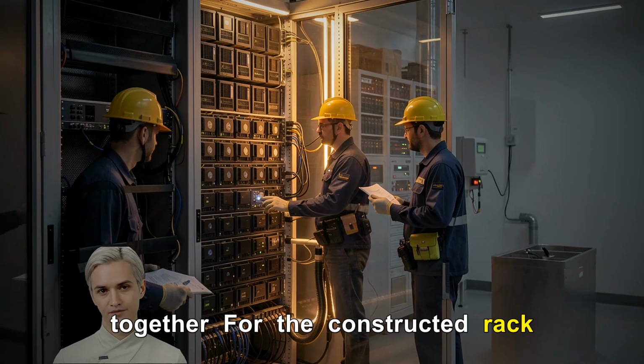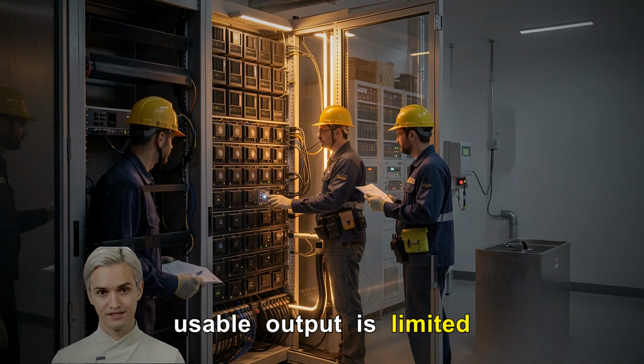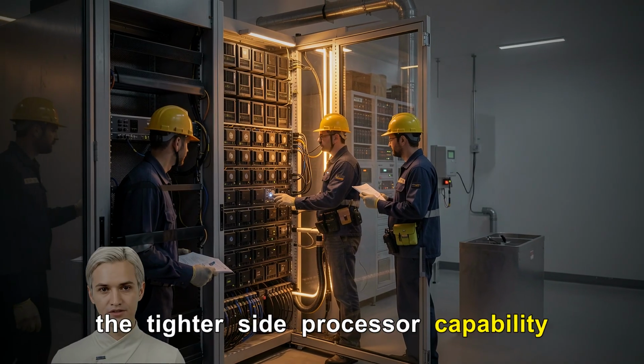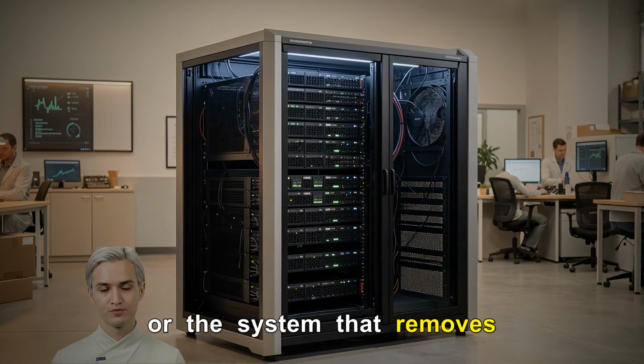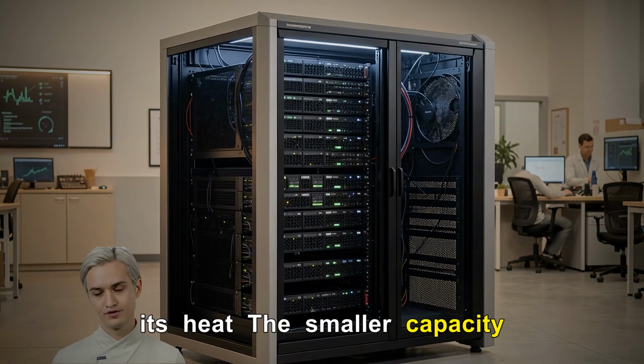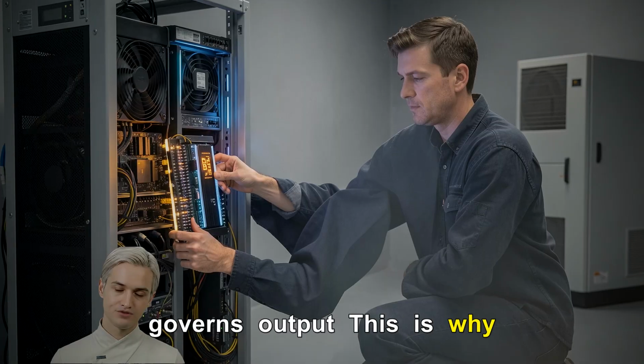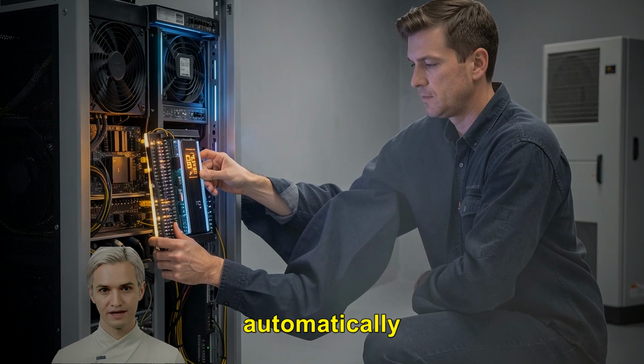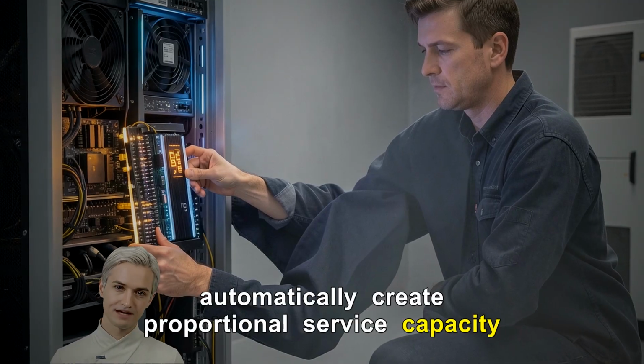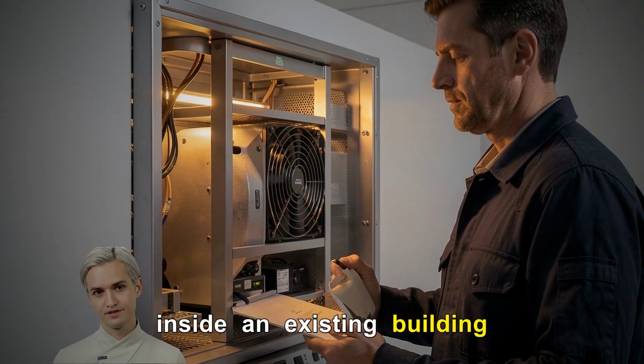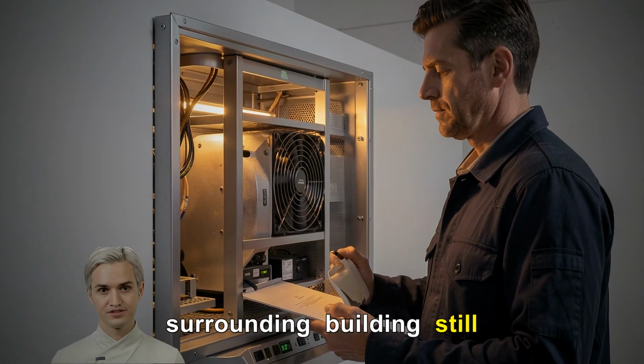For the constructed rack, usable output is limited by the tighter side: processor capability, or the system that removes its heat. The smaller capacity governs output. This is why a faster chip does not automatically create proportional service capacity inside an existing building. The surrounding building still matters.